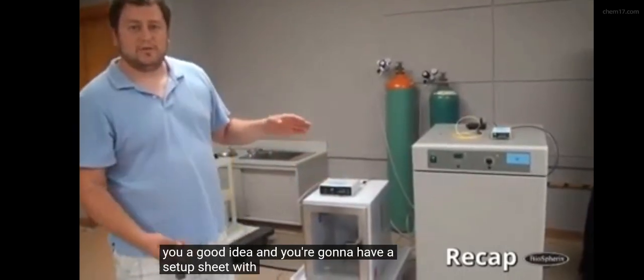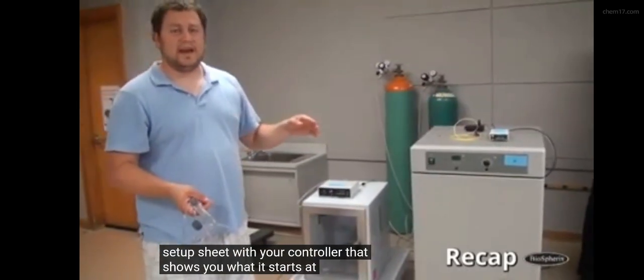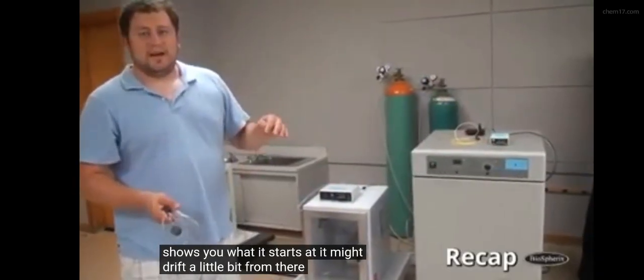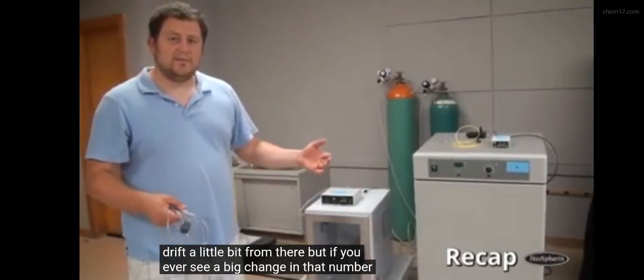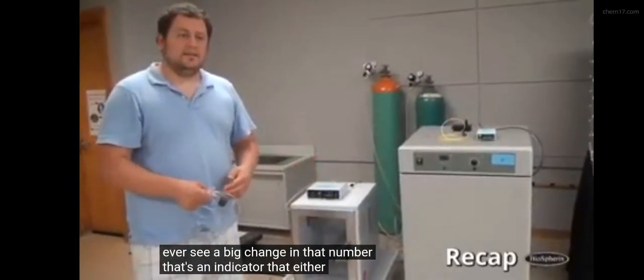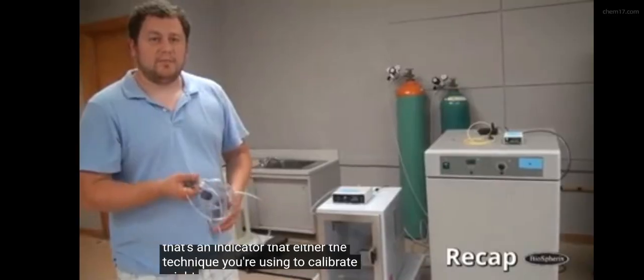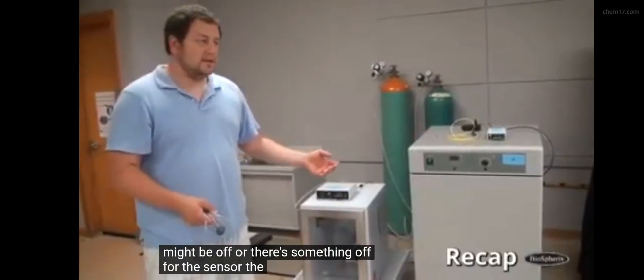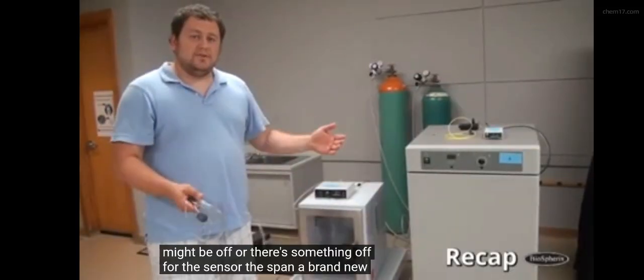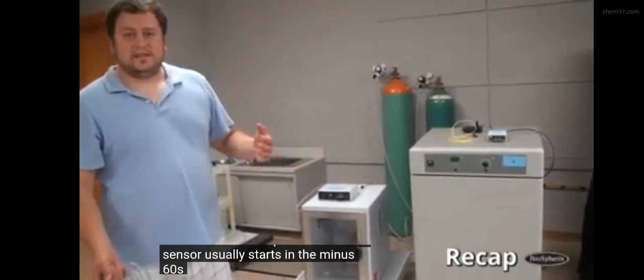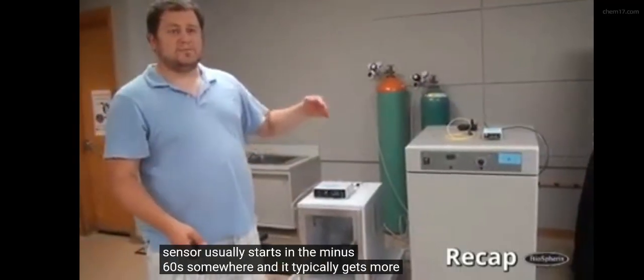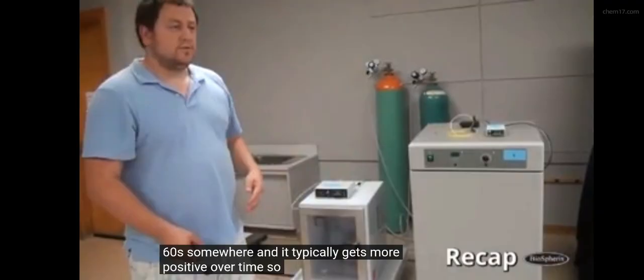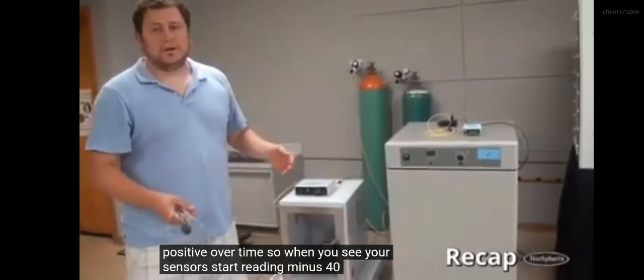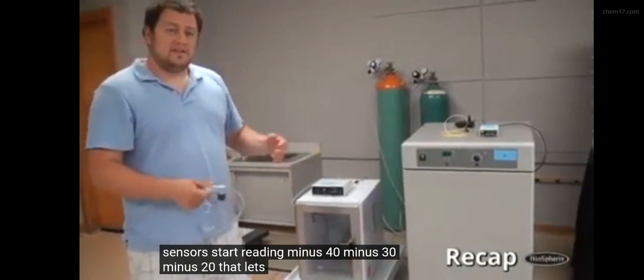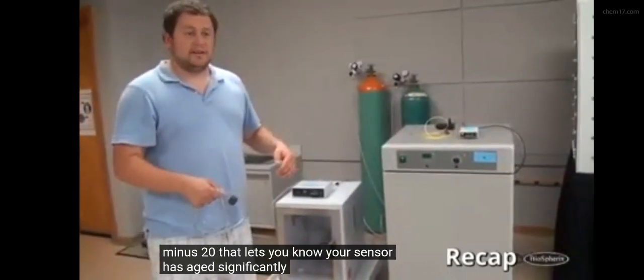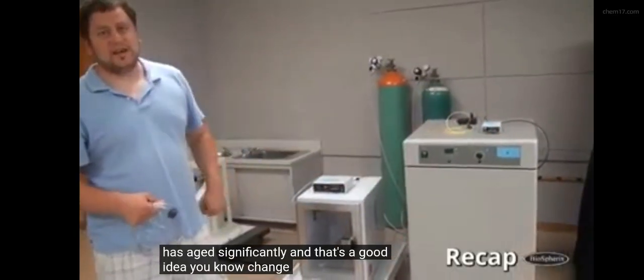And you're going to have a setup sheet with your controller that shows you what it starts at. It might drift a little bit from there, but if you ever see a big change in that number, that's an indicator that either the technique you're using to calibrate might be off, or there's something off with the sensor. The span, a brand new sensor usually starts in the minus 60s somewhere, and it typically gets more positive over time. So when you see your sensor start reading minus 40, minus 30, minus 20, that lets you know your sensor has aged significantly, and that's a good time to change that sensor out.